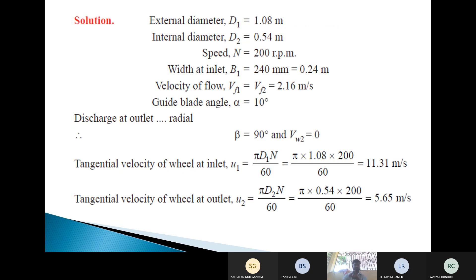Given data: D1 = 1.08 m, D2 = 0.54 m, N = 200 rpm, B1 = 240 mm = 0.24 m, Vf1 = Vf2 = 2.16 m/s, guide blade angle alpha = 10 degrees. Since discharge at outlet is radial, beta = 90 degrees and Vw2 = 0. Tangential velocity at inlet: U1 = π·D1·N/60, substituting values gives U1 = 11.31 m/s. Tangential velocity at outlet: U2 = π·D2·N/60 = 5.65 m/s.